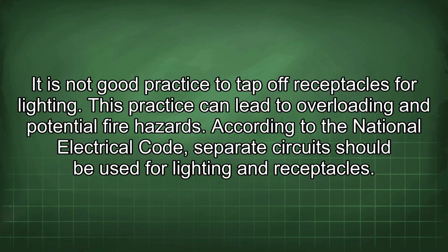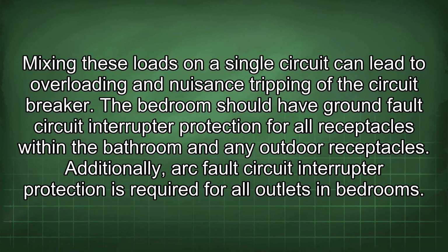This practice can lead to overloading and potential fire hazards. According to the National Electrical Code, separate circuits should be used for lighting and receptacles. Mixing these loads on a single circuit can lead to overloading and nuisance tripping of the circuit breaker. The bedroom should have ground fault circuit interrupter protection for all receptacles within the bathroom and any outdoor receptacles. Additionally, arc fault circuit interrupter protection is required for all outlets in bedrooms.